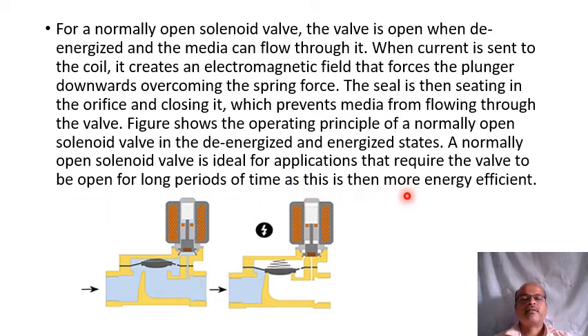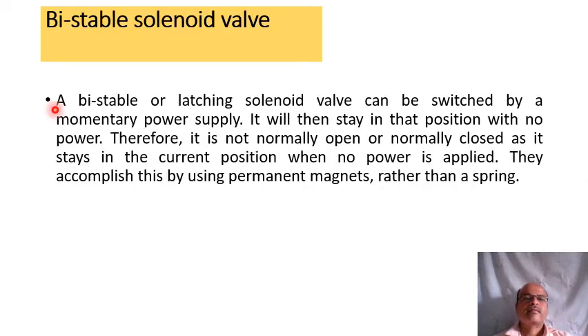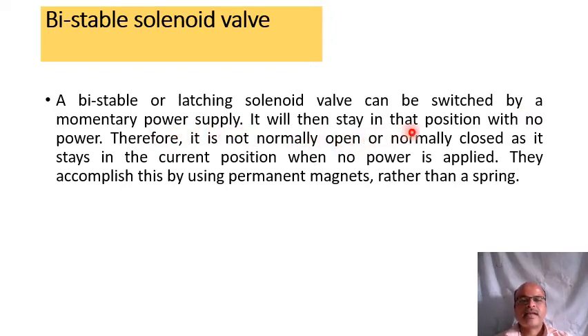A normally open solenoid valve is ideal for applications that require the valve to be open for long periods of time, as it is more energy efficient. A bistable or latching solenoid valve can be switched by a momentary power supply and will stay in that position with no power. It is not normally open or normally closed, as it uses permanent magnets rather than a spring.